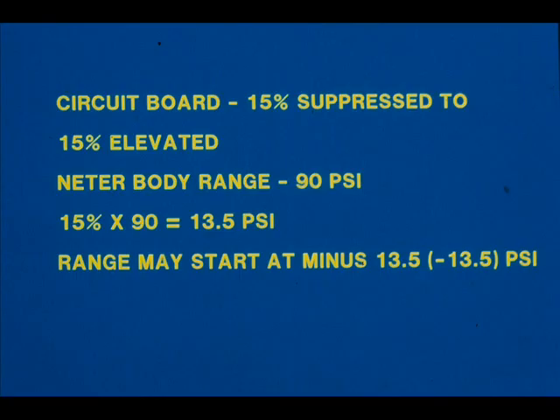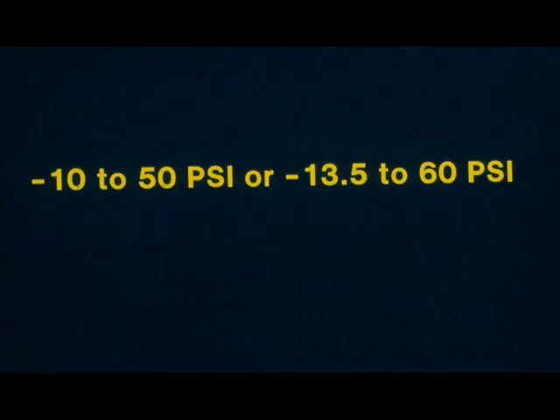The 15% elevated means that the range may be adjusted below 0 PSI to approximately 15% of the upper range limit. Therefore, it would be possible to calibrate our 90 PSI meter body and circuit board combination to a range such as minus 10 to 50 PSI or minus 13.5 to 60 PSI.